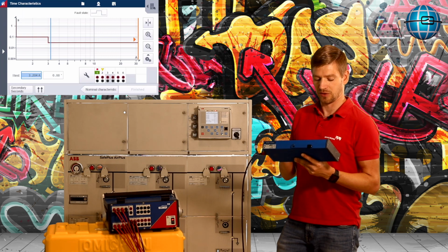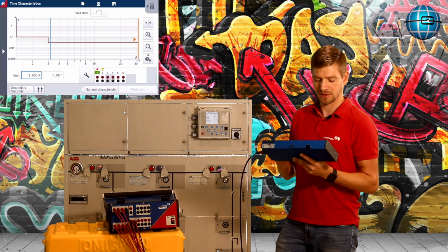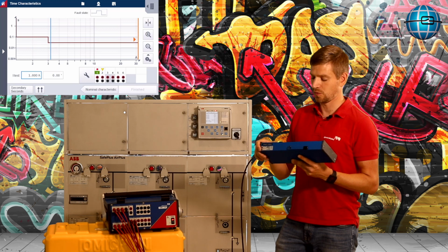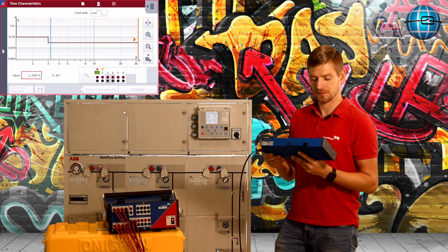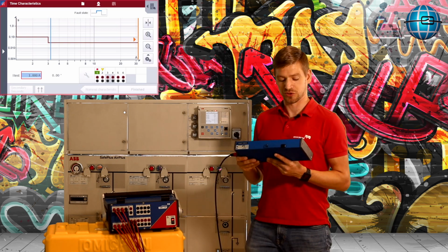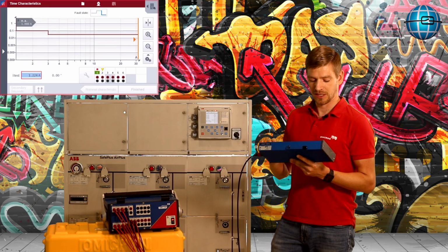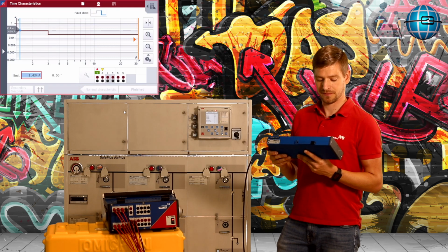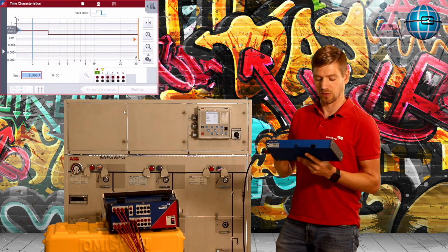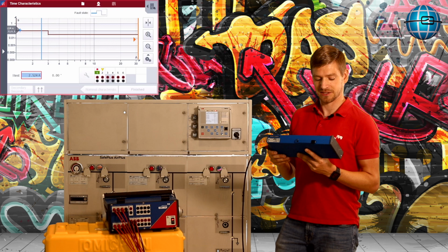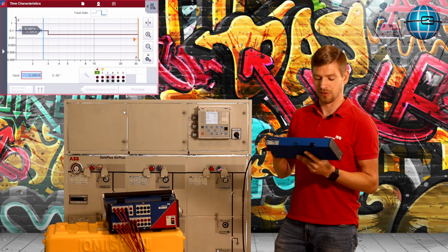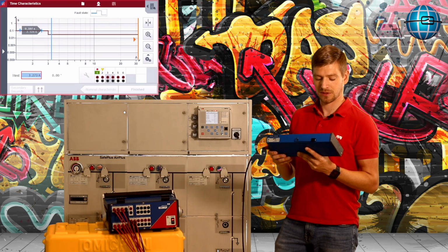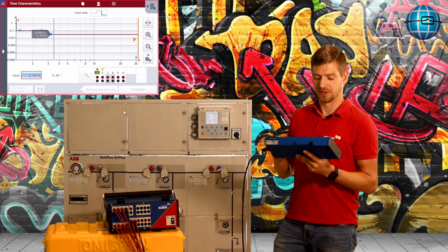Go on the test screen, and now I can place some test points with a slider, starting maybe with 1 amp for the first shot. CM control starts injection, and there should be no trip signal, perfect. And now raise the current higher than 1.3 amp. Okay, we get this trip signal. Go up near to the second stage. And let's see. Okay, again we get the trip signal. Go higher than the second stage, perfect, and now we also get a quick trip time.